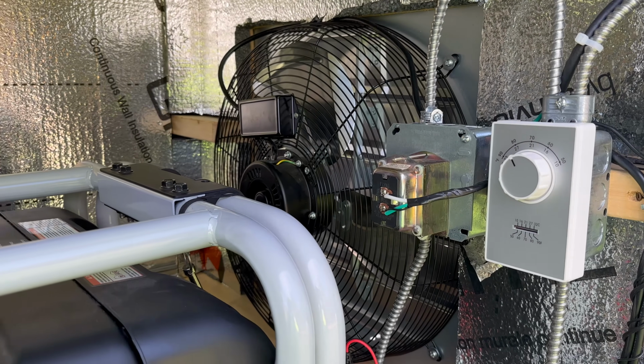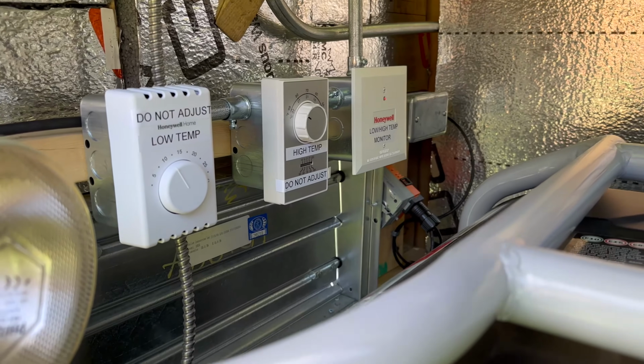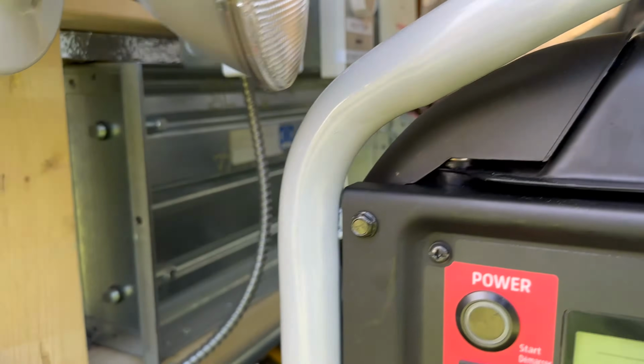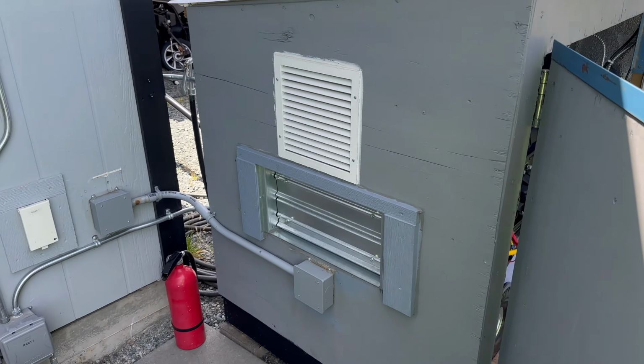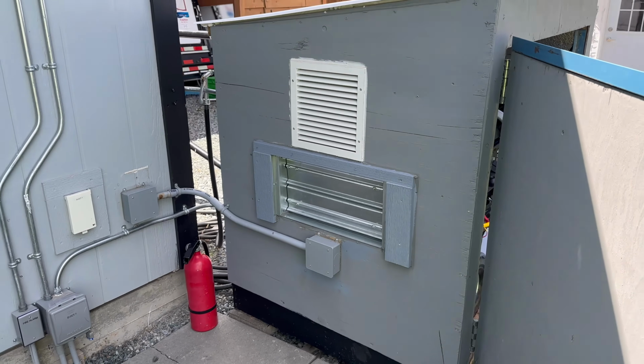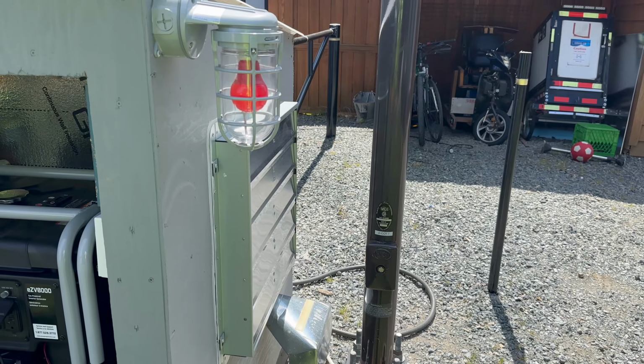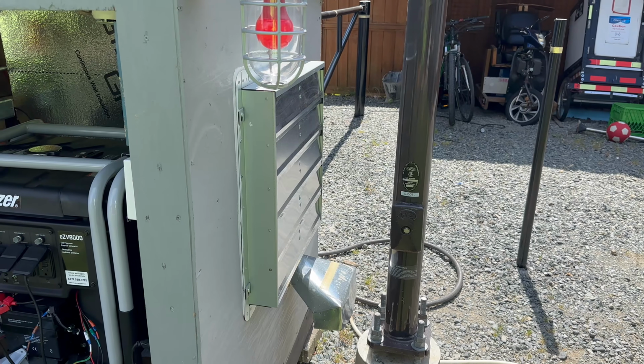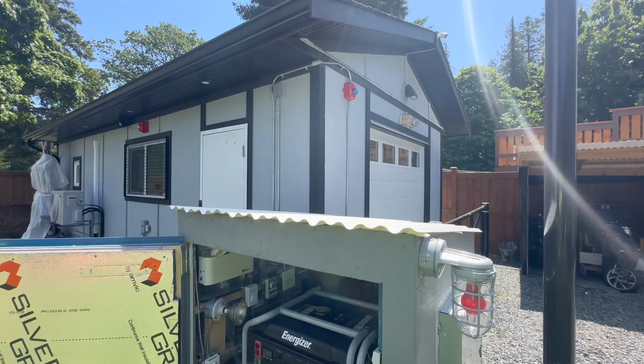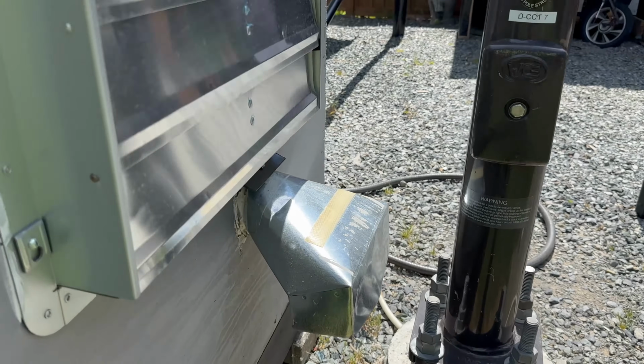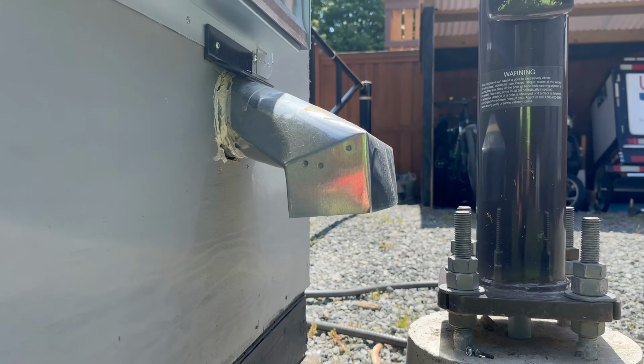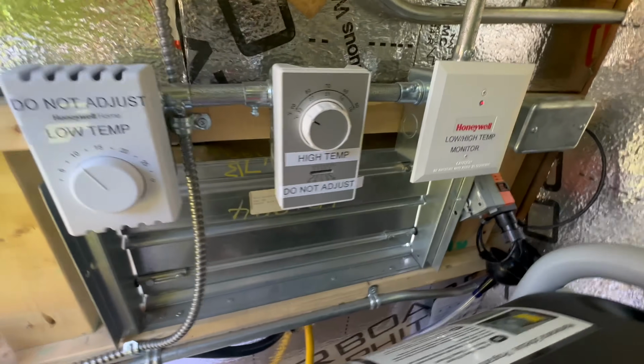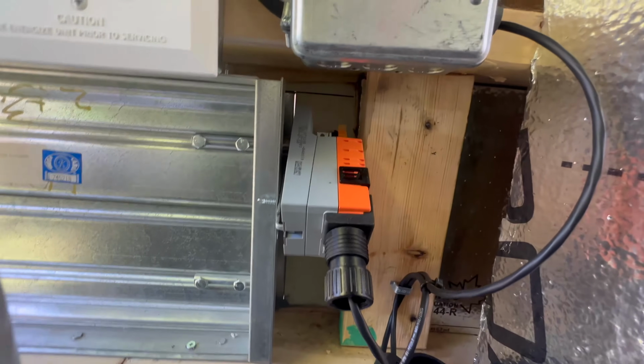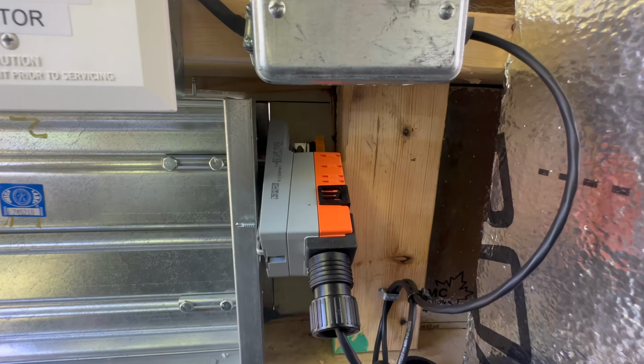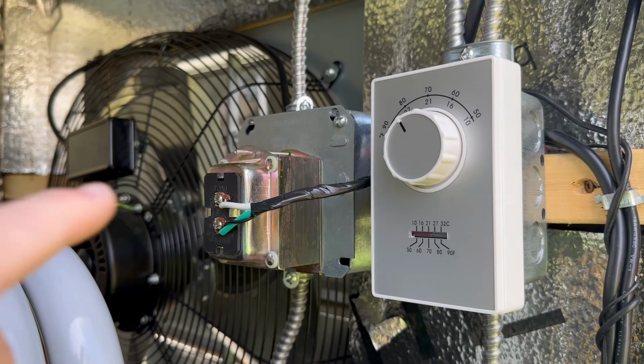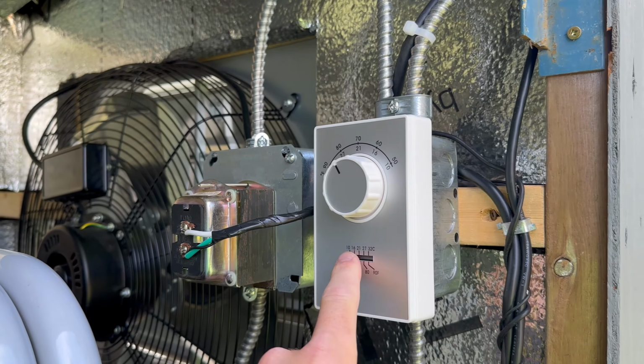To take fresh air in, I have an automatic damper installed on the other side of the building, which will draw fresh air in from this cooler side of the building and blow any air away with any exhaust gases away from the main structure, as well as make sure to not intake any exhaust fumes from the exhaust pipe. This damper uses this damper actuator mounted on the side of it, which is powered off of 24 volts off of this transformer, which is tied onto the constant power.